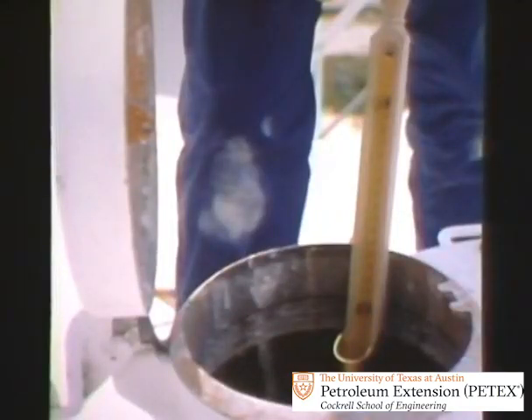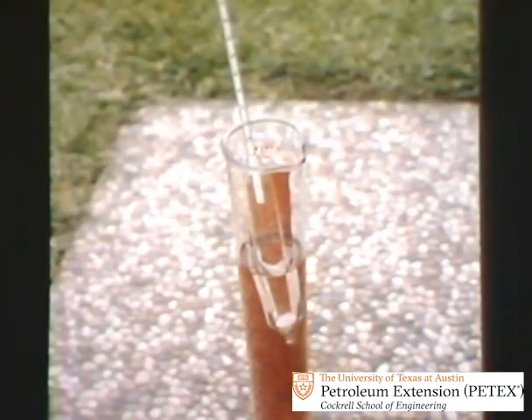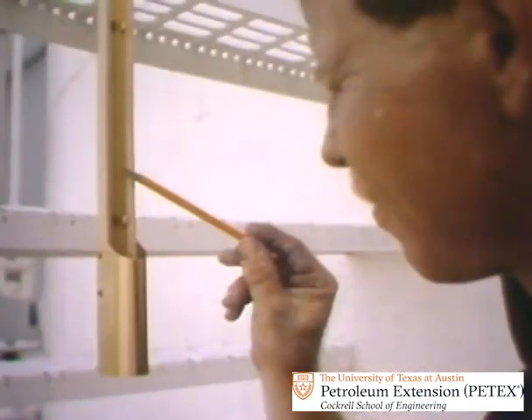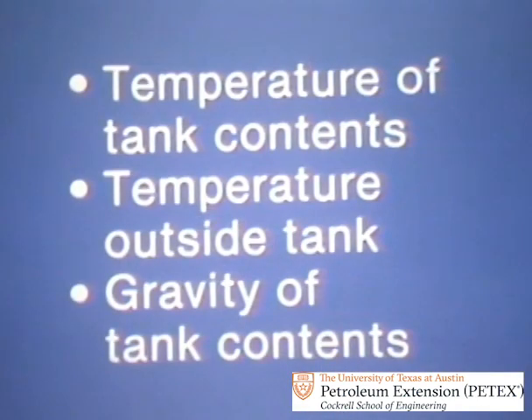Since this tank holds over 500 barrels, the crew has to make a few more measurements. These include the temperature of the tank's contents, the gravity of the contents, and the ambient temperature near the tank shell. These temperature and gravity measurements are important, and allowances are made for them in calculating a capacity table for tanks of 500 barrels or more.